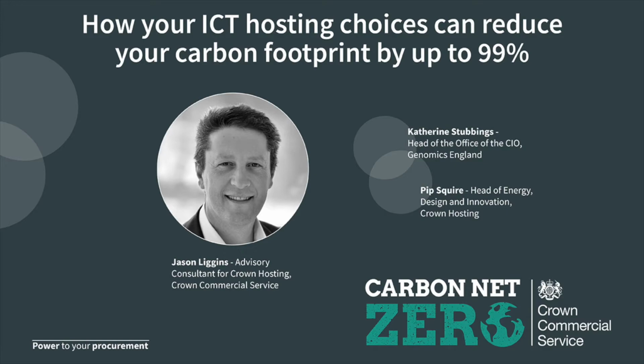How do we achieve that? Well, our cooling systems use direct fresh air with evaporative cooling. We use external ambient air because here in the UK, there's lots of it and it's free. And it comes with no carbon footprint. We filter it through operating theatre standard filtration systems before blowing it through the server rooms.